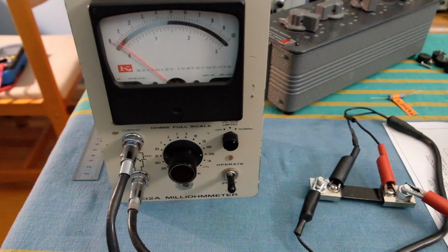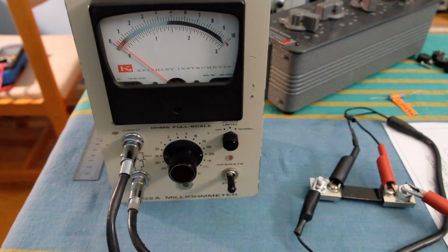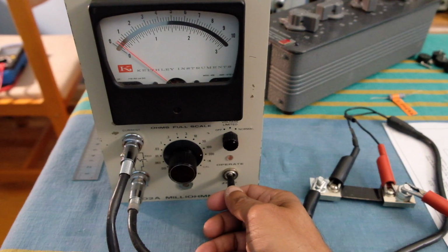So that is a limitation of even a milliohm meter that you build. If you're really looking for absolute value in that neighborhood of 0.1 and below, you really need a very good ohm meter. You may have a resolution of 1 milliohm, but that doesn't mean you can actually measure a 1 milliohm resistor accurately with these type of ohm meters or milliohm meters. This one actually will, and I think it's fairly accurate.